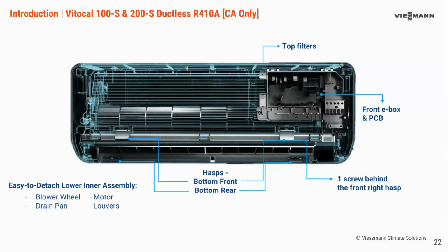So benefits: the filter is easy to remove up top, so it's actually a clip-in, like a magnetic filter that just pops in place rather than going within the unit and you having to reach over and pull up and out. The e-box electronics are front and center rather than being tucked in and requiring you to remove a lot of components to access, so you have easy access to the electronics. And the biggest thing, as I mentioned, is the blower wheel assembly being removable so easily. That gives you access to the blower wheel, the drain pan, the motor, the louvers, and the louver motors themselves. So there's 2 clips up top, 2 clips on the bottom, and there's 1 screw behind that right clip, and you can pull out the entire assembly.